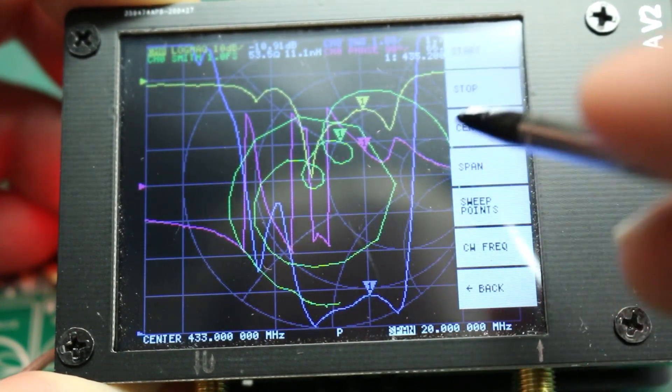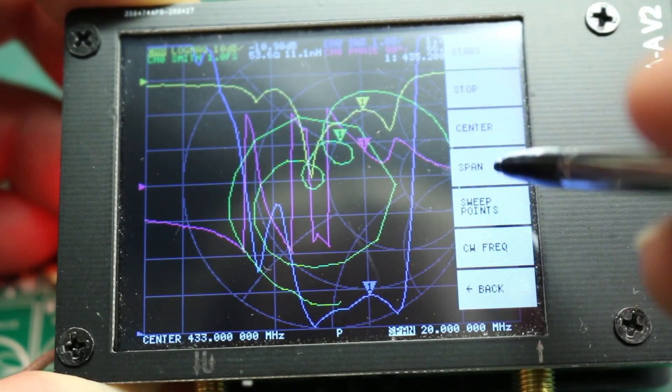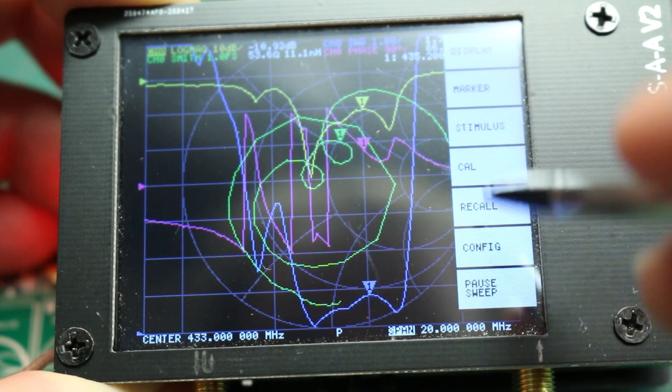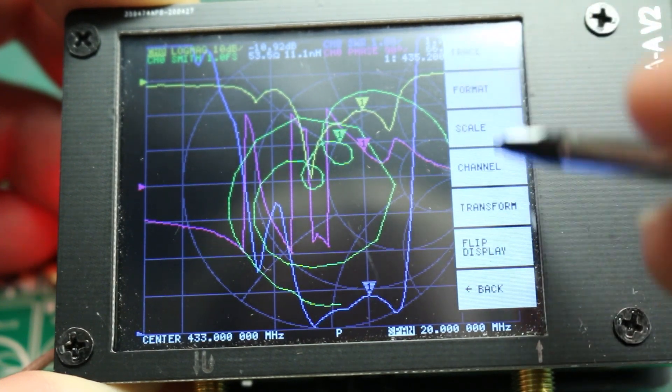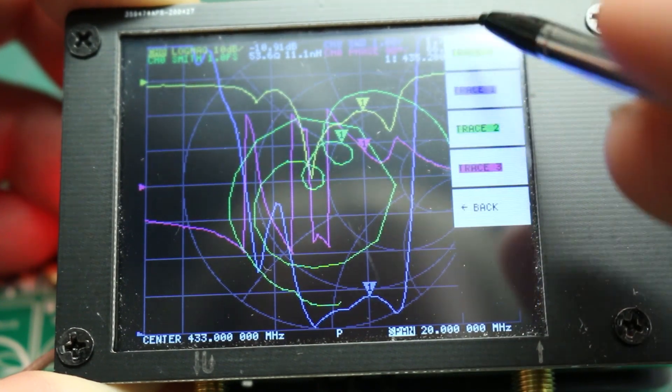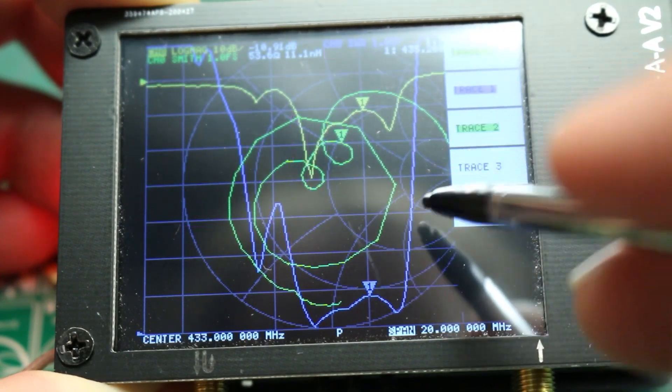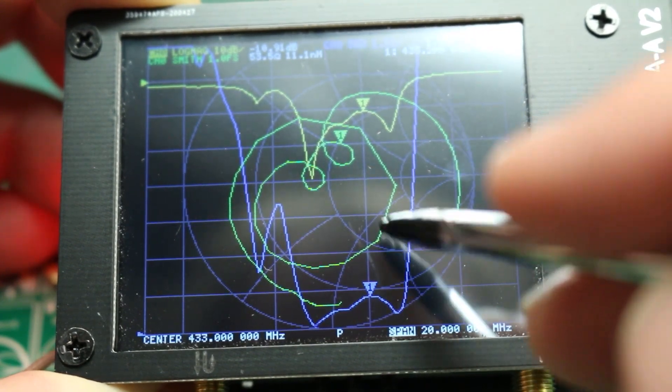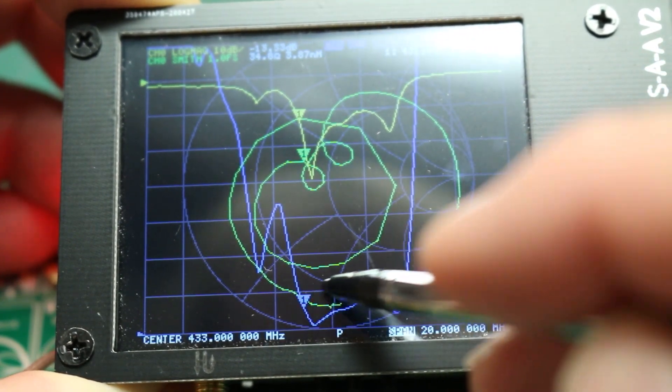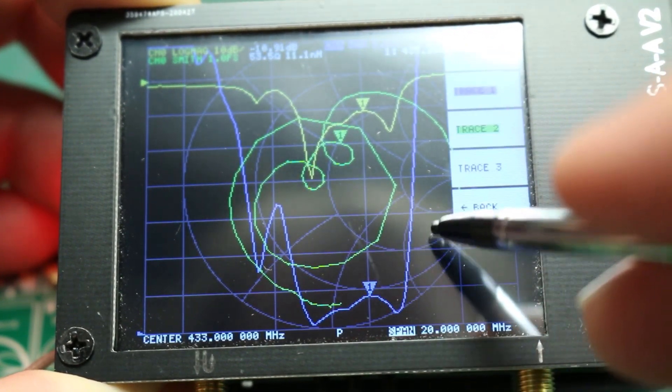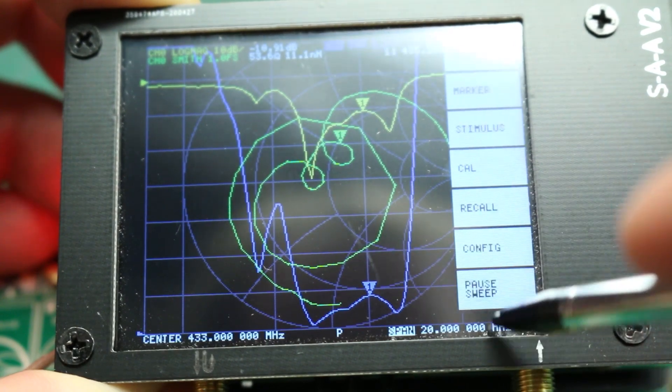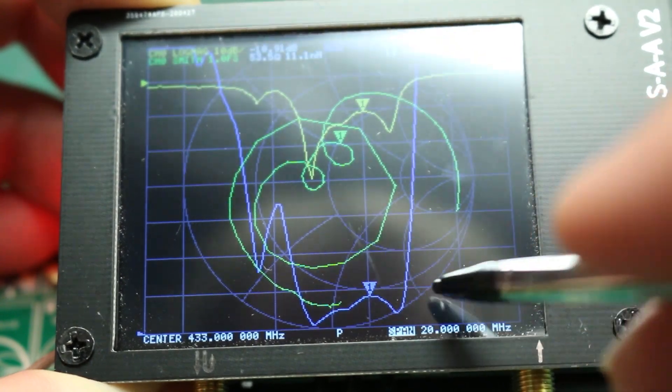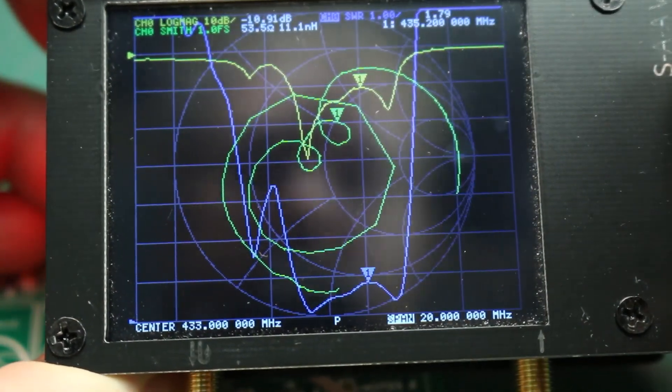And then if you zoomed in to, say, 500 MHz span, you would only have a tiny portion of your available measurements. So, any time you change a setting, run a new calibration.